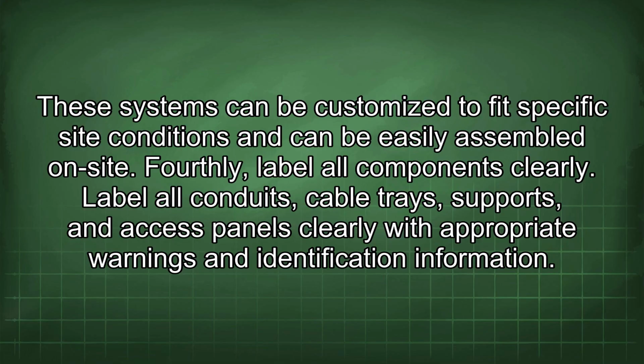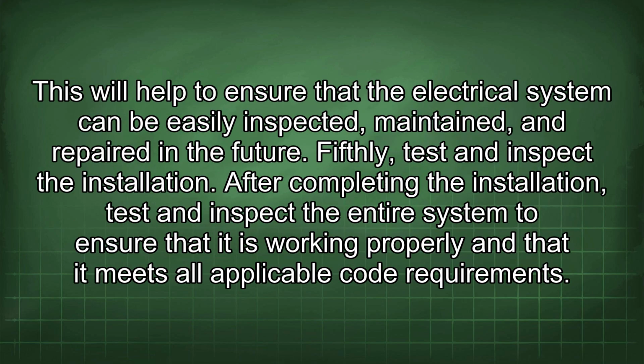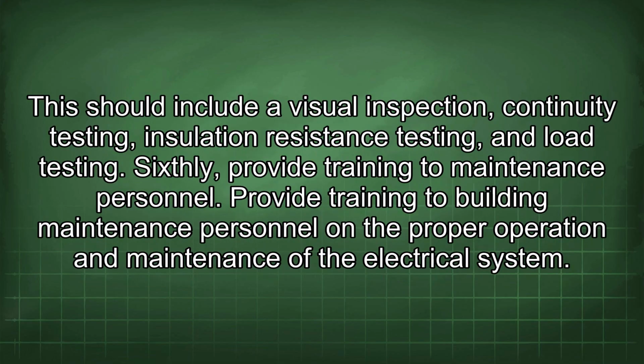Fourthly, label all components clearly. Label all conduits, cable trays, supports, and access panels clearly with appropriate warnings and identification information. This will help to ensure that the electrical system can be easily inspected, maintained, and repaired in the future. Fifthly, test and inspect the installation. After completing the installation, test and inspect the entire system to ensure that it is working properly and that it meets all applicable code requirements. This should include a visual inspection, continuity testing, insulation resistance testing, and load testing.